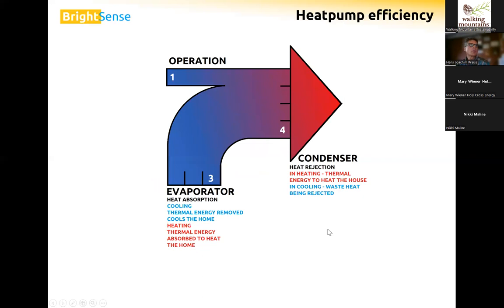Quickly on the heat pump efficiency, where we are on the evaporator, where we are absorbing our thermal energy, we are adding the operating energy that is required to run the piece of equipment. And then we have the usable thermal energy in heating. In this example, we are absorbing 3 units of energy. We are adding 1 from the operating side, and we get 4 units of usable energy delivered for our space heating. So in this case, 4:1 would be our coefficient of performance, 400%, or a COP of 4.